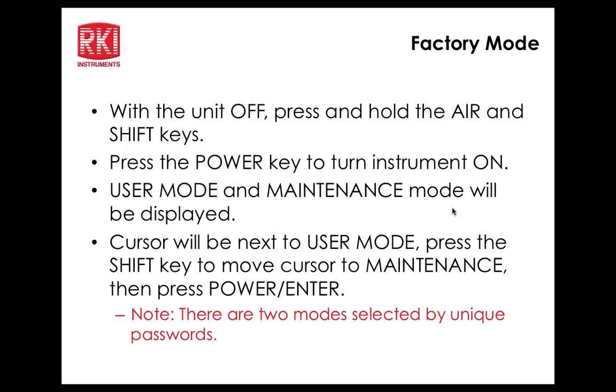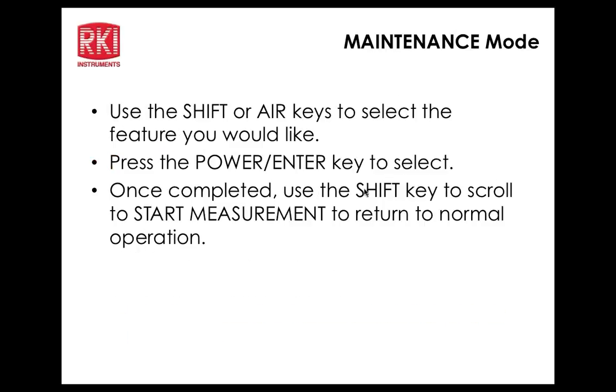Yeah, what question is that? In the maintenance mode, there's an item that says CO display in the leak check submenu, and that's where you turn the CO sensor display on or off when you're in leak check mode. Now, the sensor's always on -- it's just whether or not it's showing up on the display.